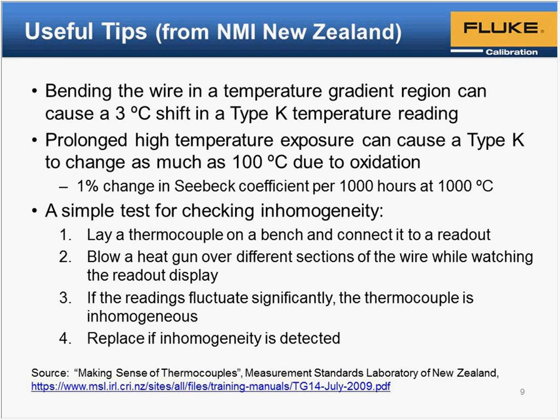They spent a lot of time studying type K wire and observed as much as a 100-degree change in output over 1,000 hours of exposure at 1,000 degrees C. There are some techniques out there to stabilize K wire by putting it in a non-oxidizing environment, flooding the wire with argon or something to protect it so it won't drift or change much. And they also describe tests for checking wire consistency or inhomogeneity.